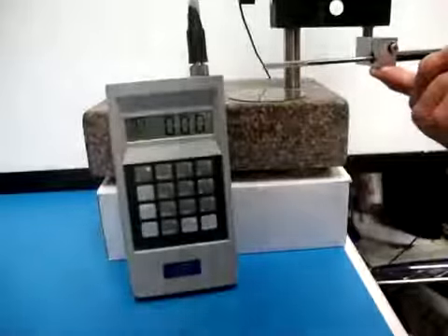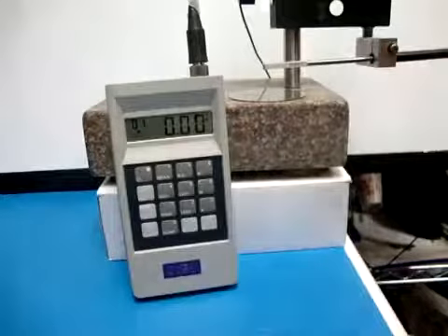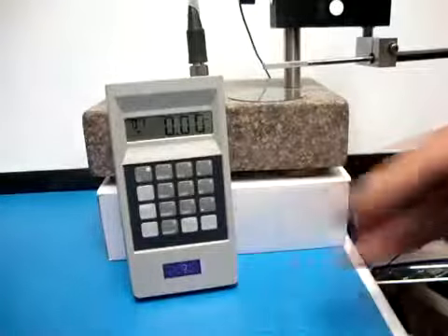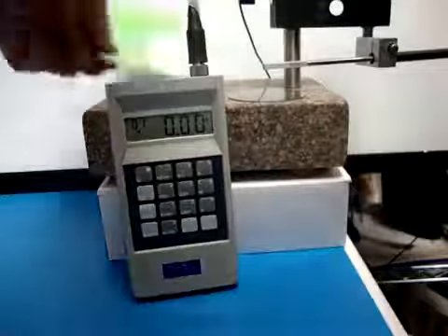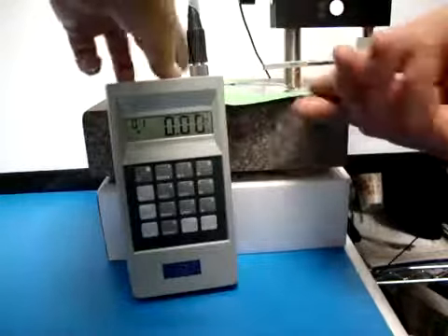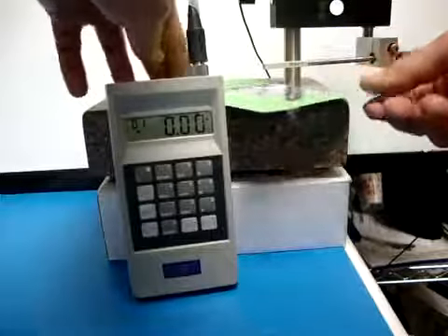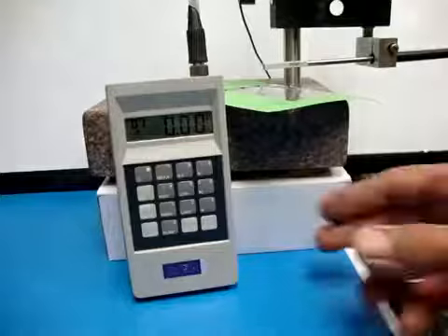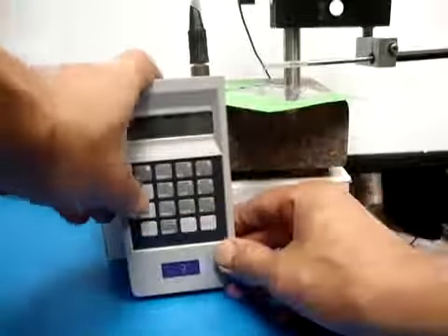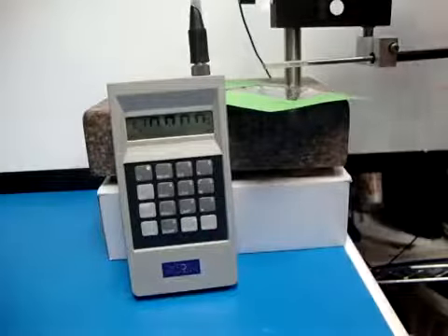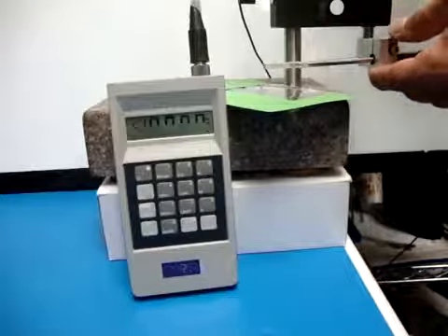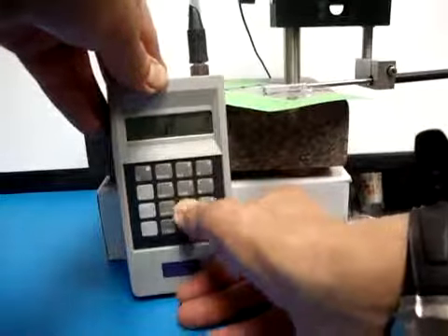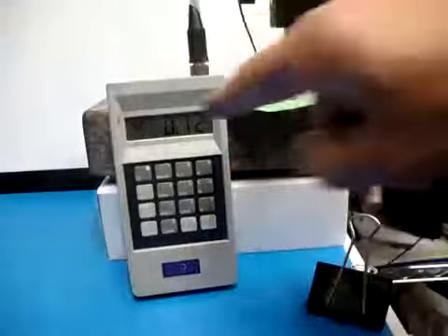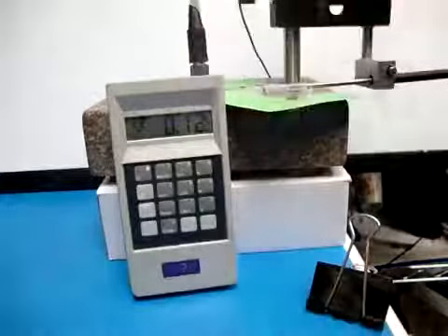Okay, so then I'm going to hold the probe up above the base again, and I'll grab my first shim, which in this case will be a 0.2. Not much room for that, but okay, so now we hit star cal, and now it's looking for the first calibration shim, C1. So I'll place it down on the base, and I'll enter the value of the shim, which is 0.2. Enter. So now you can see it's asking for the second calibration shim, C2.